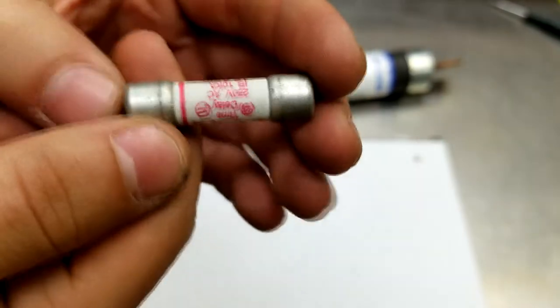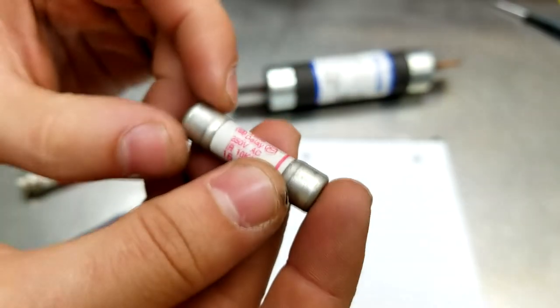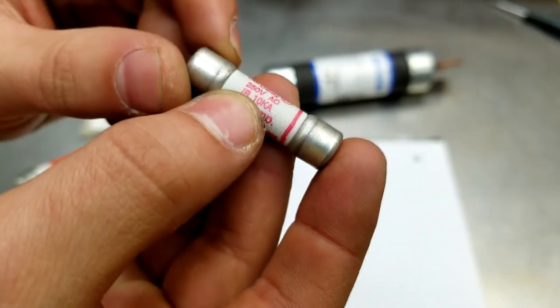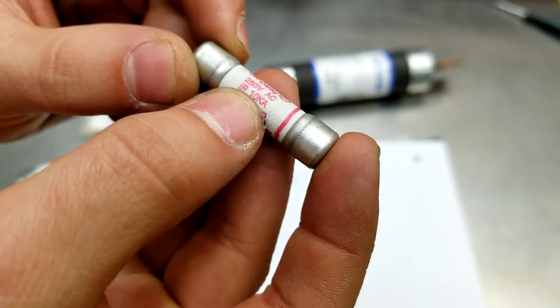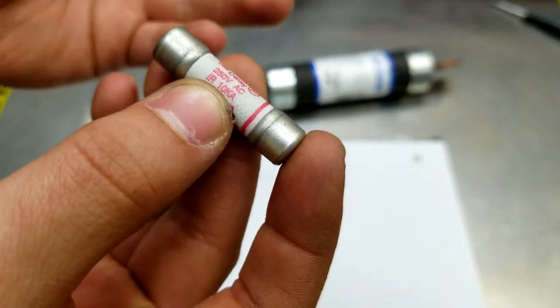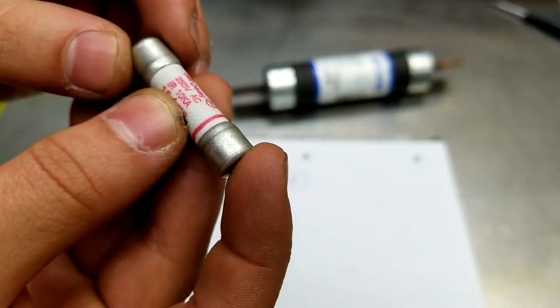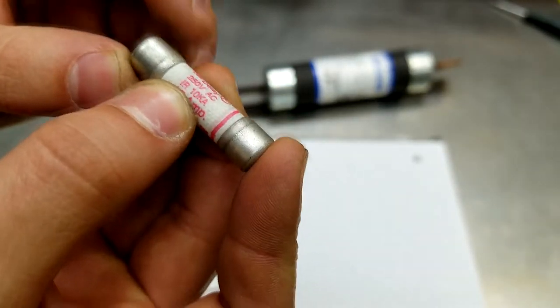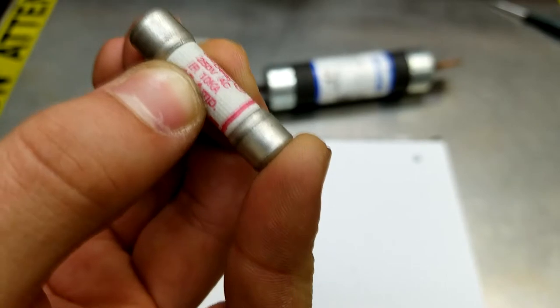So to solve that problem, we use a HRC fuse. And that's right. So this puppy has a different type of rating on it, and that is this: IR 10KA. Now what is KA? Kiloamps. That's right. This little fuse can stop 10,000 amps current flow.